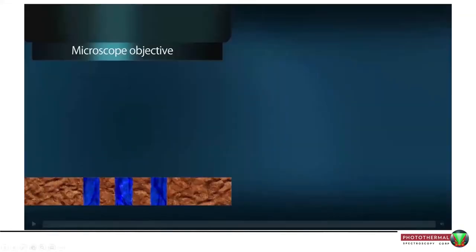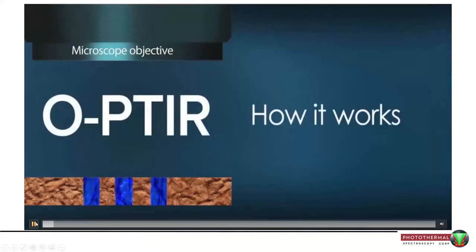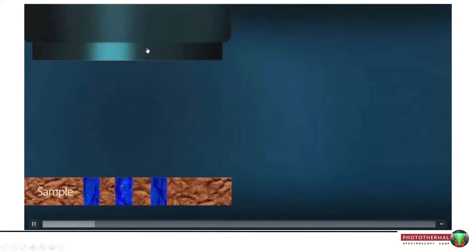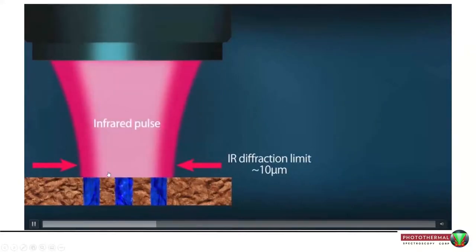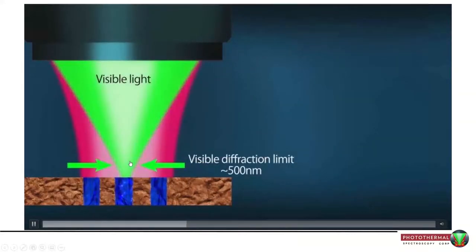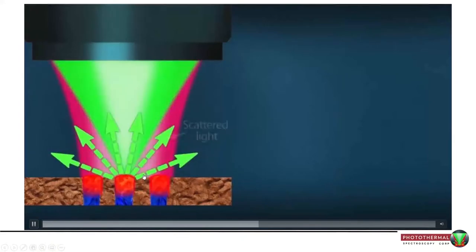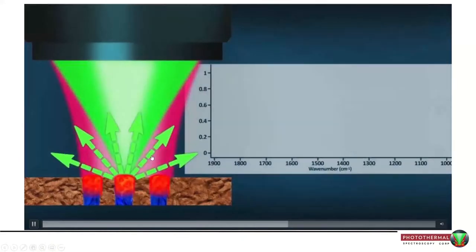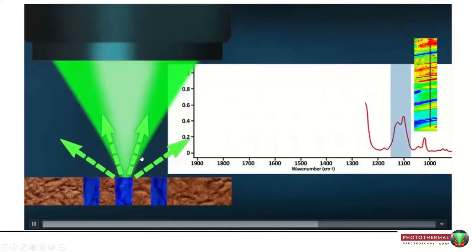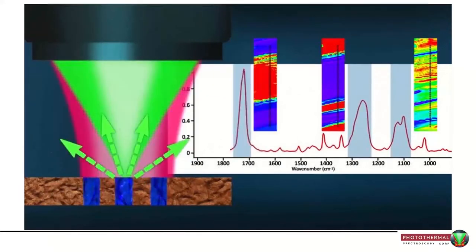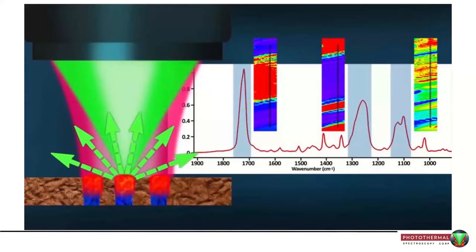How does this technique work? It starts with a reflective Cassegrain-style microscope objective, through which we shine a pulsed infrared laser beam — being infrared, it's fairly broad, maybe around 10 microns. At the same time we shine in our probe, the green beam at about 500 nanometers. The infrared generates thermal expansion, and that thermal expansion changes the way the green light is reflected or scattered back. As we tune our infrared laser from one wavelength to another, we monitor the intensity of the green light reflected back, and from that we calculate out a pure infrared spectrum collected in reflection mode.